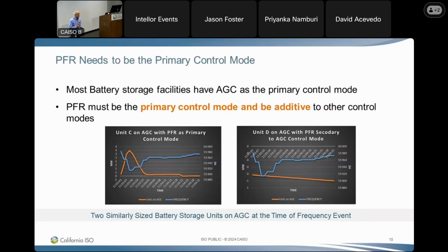So please make sure that primary frequency response is your primary control mode on your controllers, and it has to be additive to whatever the set point is. So if the AGC has you operating at, let's say, 20 megawatts, and a frequency event happens and you're obligated to provide 1 megawatt, you go to 21 megawatts. So it's additive. It doesn't replace it.